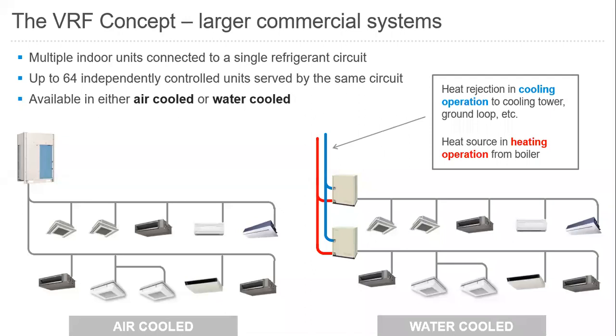Not only do we have an air-cooled option, but we also have a water-cooled option. One of the unique things about the water-cooled option is that we're going to have a ground source or another water source, such as a lake or cooling tower, tied to that outdoor unit through a heat exchanger. That outdoor unit is going to reject heat to that water source, whatever that is, when we're talking about the water-cooled VRF system. And we'll also add a boiler to that system so that we can keep our temperature constant year-round and provide the best efficiency possible. So once again, that's a water-cooled VRF system. The only difference is we're rejecting heat to water as opposed to rejecting heat to the air like we would with an air-cooled system. And once again, we have multiple indoor units tied to a single outdoor unit, and we're able to provide comfort cooling in individual spaces.